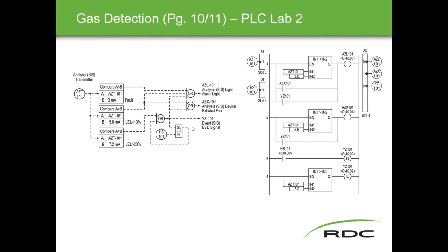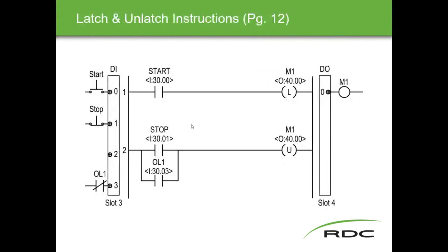The latch and unlatch instruction holds true until it is told to unlatch, using the same address for both. Pressing start energizes the latch bit which turns on the motor. Pressing stop energizes the unlatch to turn it off. This is a basic motor start-stop circuit — electricians would want to see overloads included here as well.